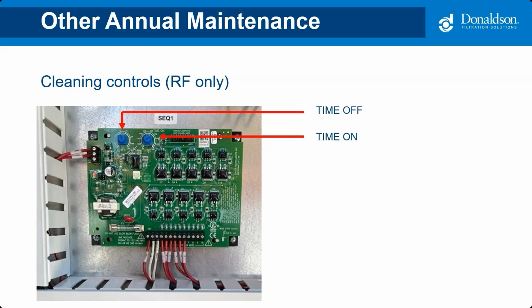This is another more technical one that I wanted to highlight. The way a dust collector pulsing system works is it is designed to have a certain time on and time off of pulsing. It is designed with very specific time sequencing, and that sequencing is adjustable in the control panel. And similar to when I said I sometimes see where people adjust the air pressure down below spec for the collector, I've also seen where people have gone into the control panel and adjusted the pulse timing. And you really don't want to do that. Of course, you want the system to be set up to run the way it's designed.